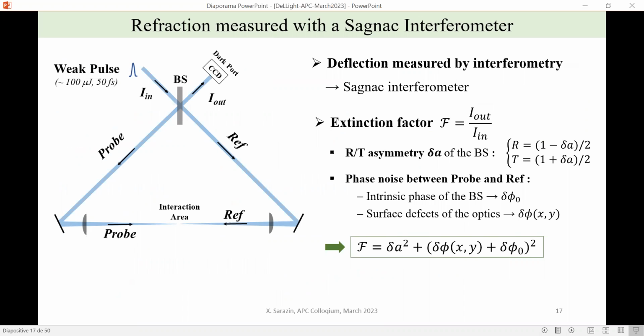So this interferometric method is based on the use of a Sagnac interferometer. So what is a Sagnac interferometer? It's a closed interferometer. So you have here a beam which enters inside the Sagnac interferometer. Half is reflected, half is transmitted, and both are reflected by two opposite mirrors and come back and interfere again in the same beam.